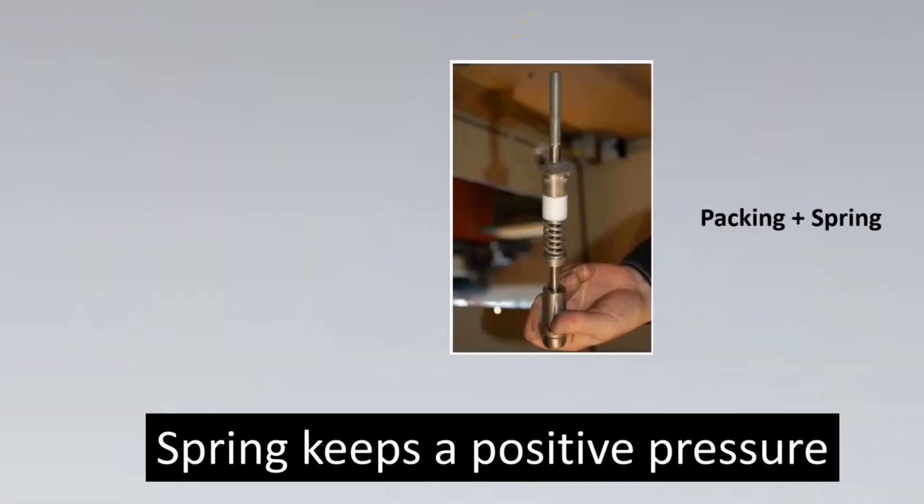If you want to see a real-life example, see here the white thing is nothing but your packing, which seems to be PTFE as we said it's white in color, and you can see a spring assembly also. It puts a positive pressure to keep the packing in place. But still there could be certain issues like the spring has failed or the tension is reduced.